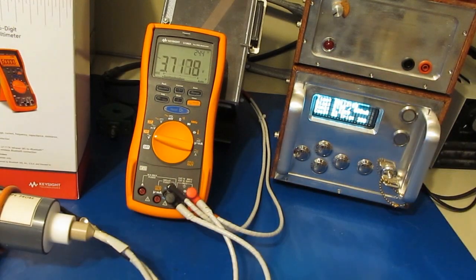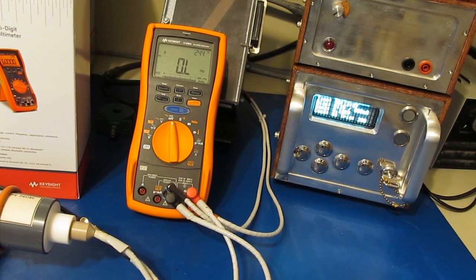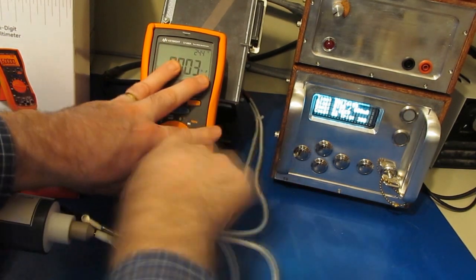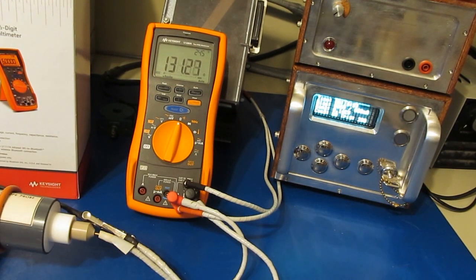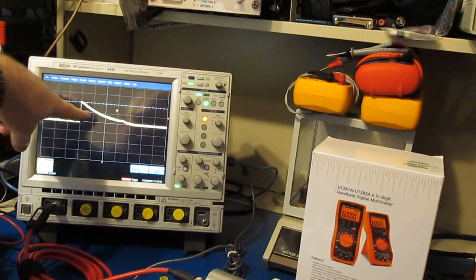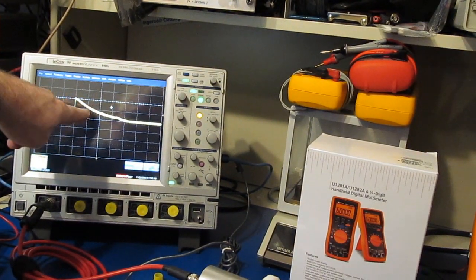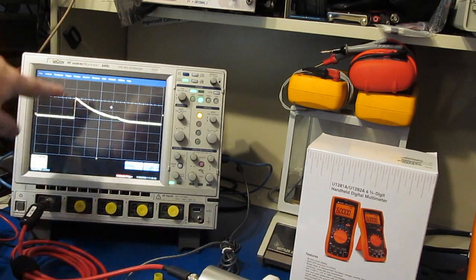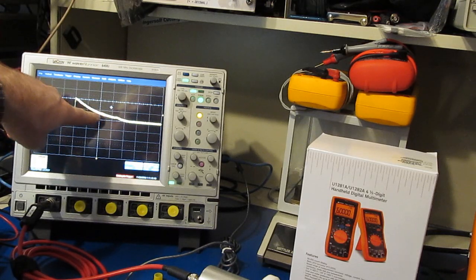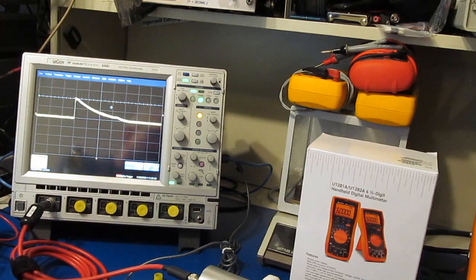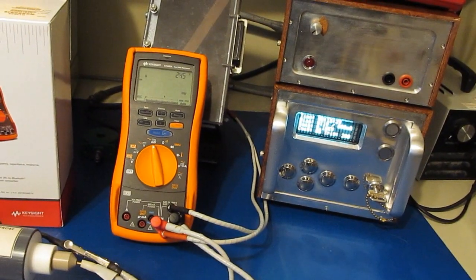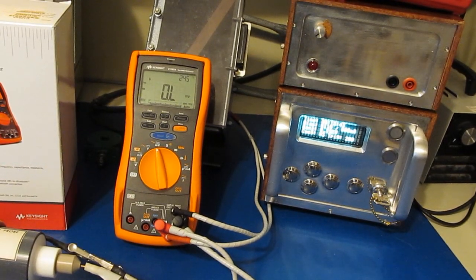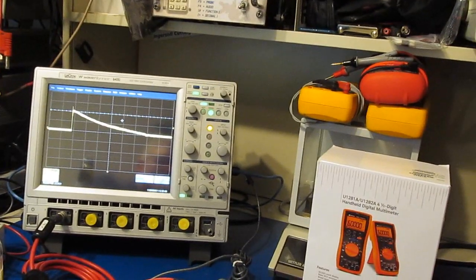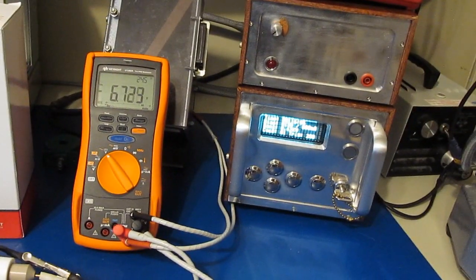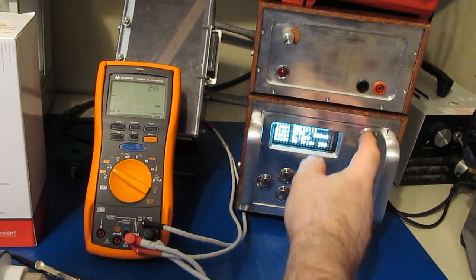So here we go. This is with the meter obviously attached. You can see that the full width half height changes a little bit. Again, this is because it's now on the ohms mode, so that's going to engage the PTC as well as that high speed clamp. But there's no sign of it breaking down at all. Again, when it breaks down, first of all, we'd hear it, but we'd also see that full width half height reduce quite a bit. You can see the difference with it in voltage mode, how wide the pulse is. Again, that's because the high-speed clamps are not engaged.